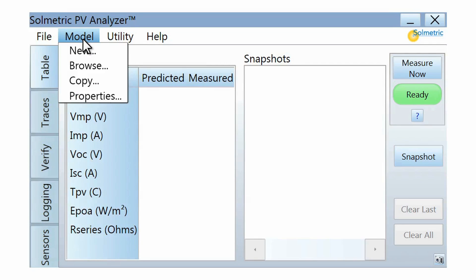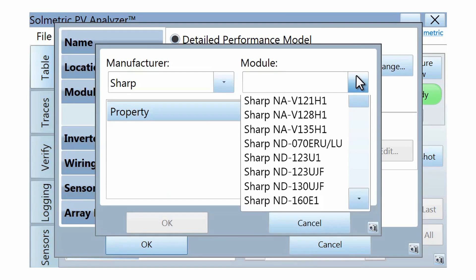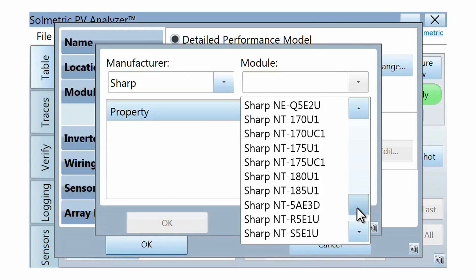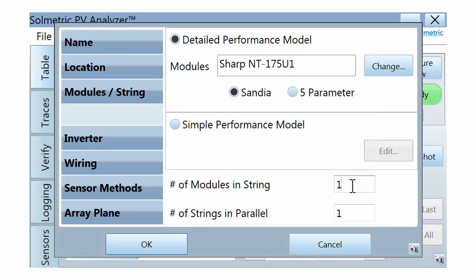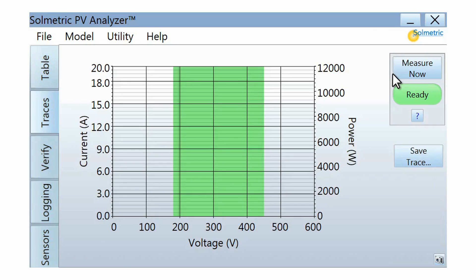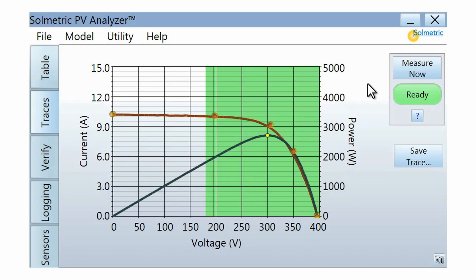The performance model is set up in preparation for measurements. It involves selecting the PV module model from an onboard database and entering the number of modules in series and in parallel. Using advanced performance models, the PV Analyzer software will generate accurate model points against which actual IV measurements can be compared.